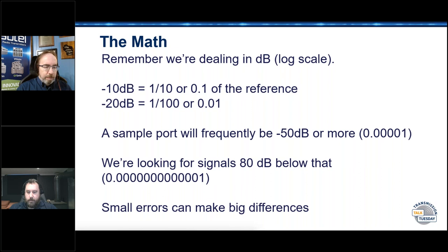Take it down 40 dB or so with a notch filter, which I'm spoiling probably the next slide. But it basically allows for better response out of the analyzer, because we're suddenly not trying to reach, we're not measuring 80. We're only comparing it against a minus 40 input. So we can make better use of what range the device has.